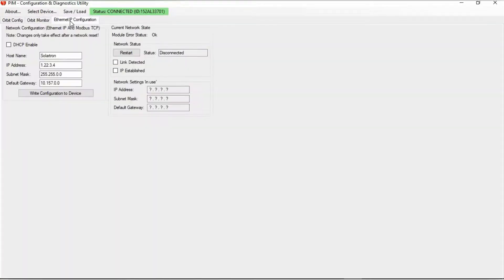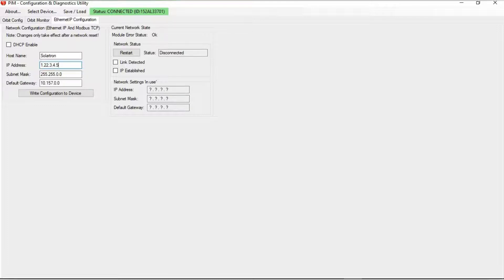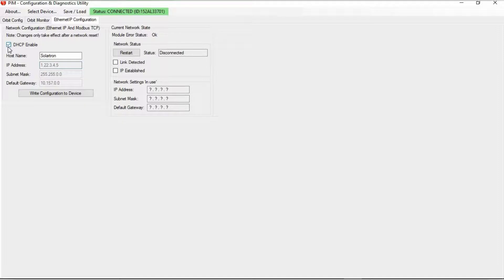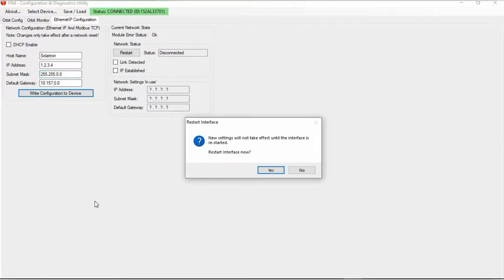Then the third tab here is the configuration. And in this case, this is the ethernet IP configuration. Now if you'll see the network configuration, you have the host name, you have the IP address, and this is where actually manually, if you want to enter it, you can do it right here to whatever number suffices. Or if you want the network, if the PIM is connected to a network and you want that to assign an address, then you just click this box. DHCP means dynamic host configuration protocol. And again, you have a host name, IP address, subnet mask, and default gateway. Then once you have this all set, you can click write configuration to device. Click yes.